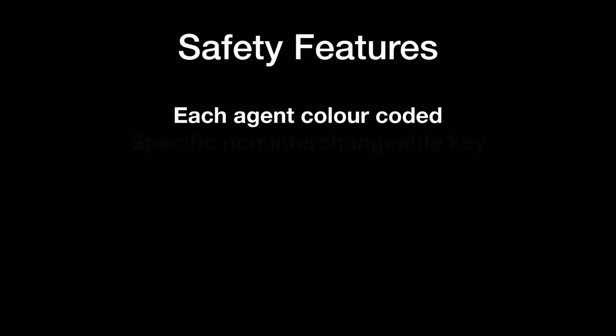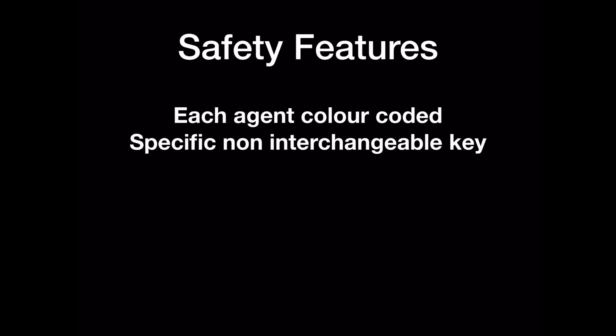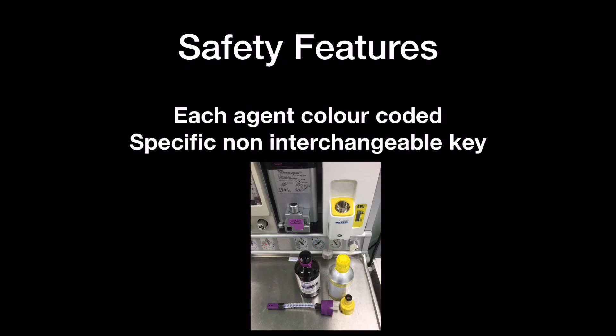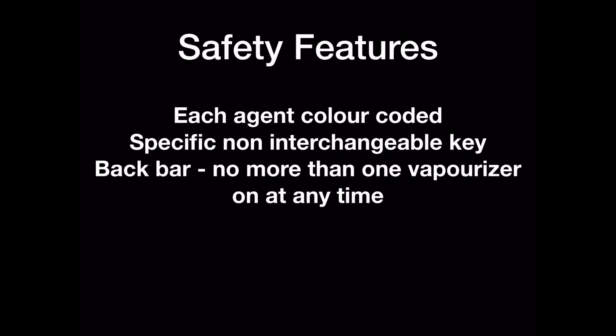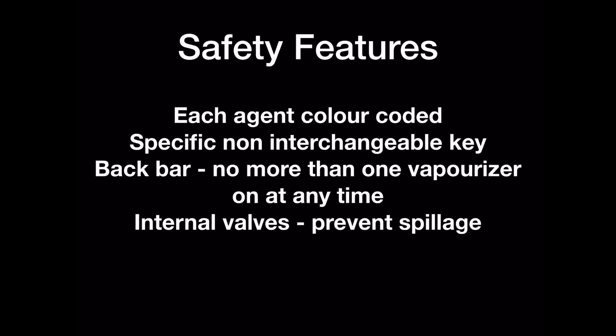Safety features: each vaporizer for each volatile agent has a different color — for example, sevoflurane is always colored yellow. Each volatile-specific vaporizer is filled with a different non-interchangeable key, so one cannot fill, for example, sevoflurane with isoflurane. Only one vaporizer can be switched on at any point the anaesthetic machine is on, secondary to the mechanism of interlocking bars on the anaesthetic machine. The vaporizer also has internal valves that prevent spillage if the vaporizer is knocked over.